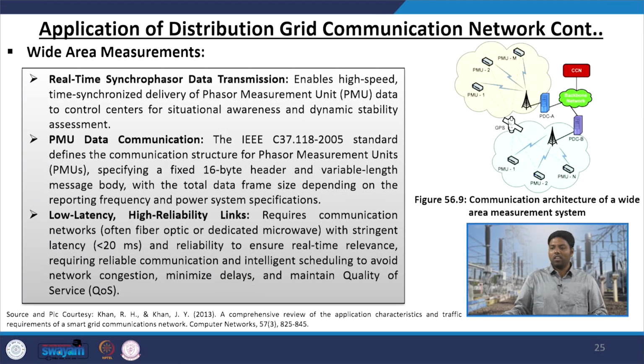Wide area measurement is also needed, using communication developed over recent years for sending synchrophasor data from the transmission system, with PMU data communication following the IEEE C37.118-2005 standard, specifying a fixed 16-byte header and variable length message body, with total data frame size depending on reporting frequency and power system specification.